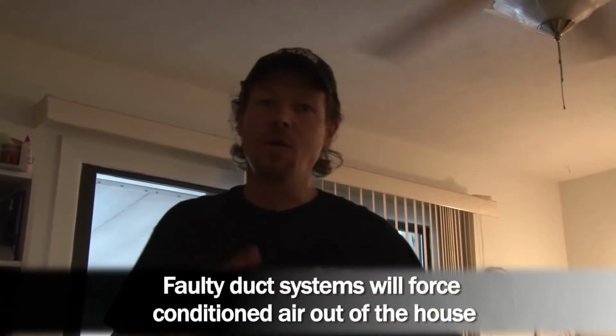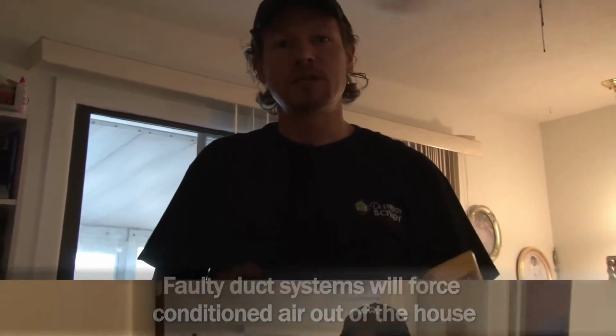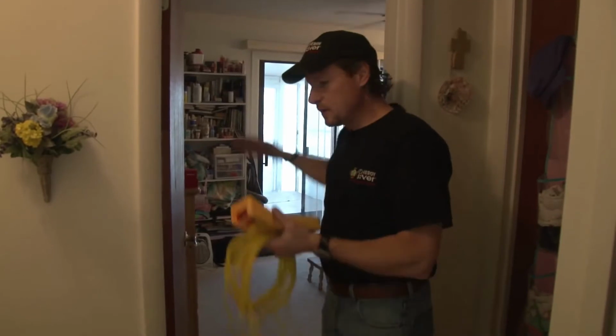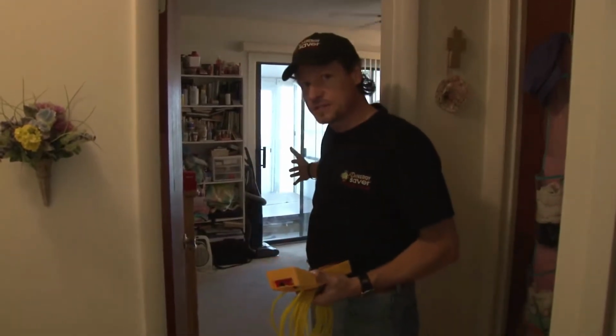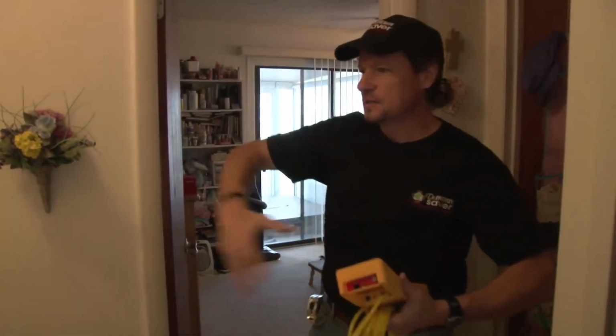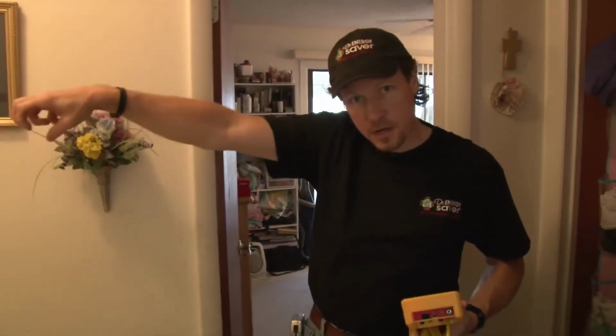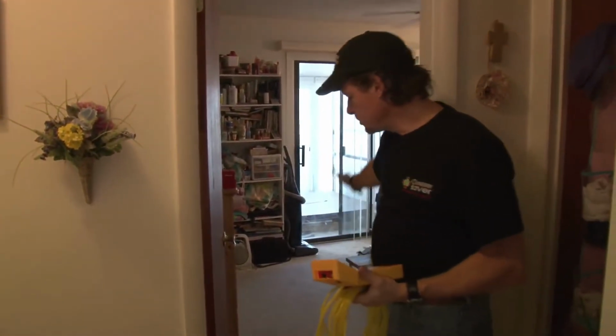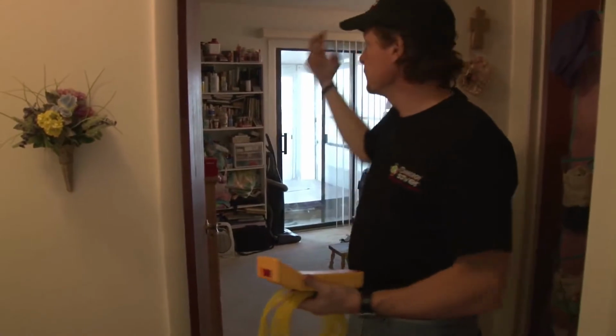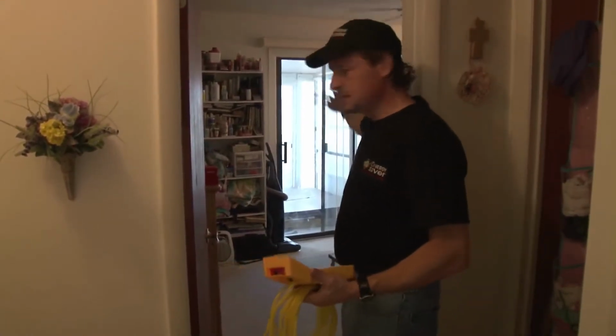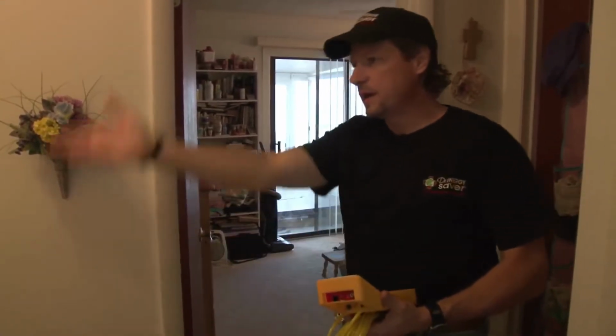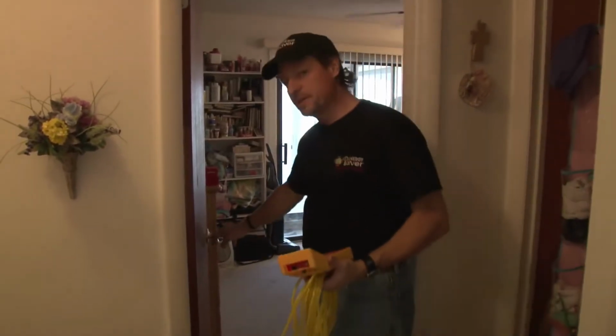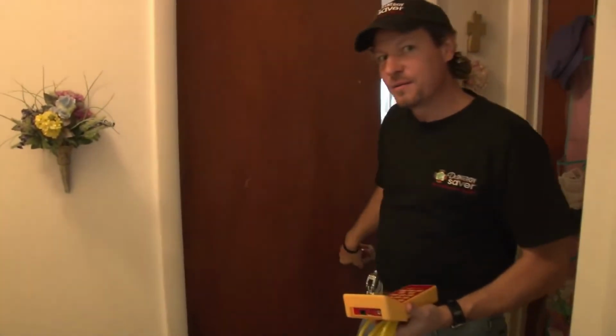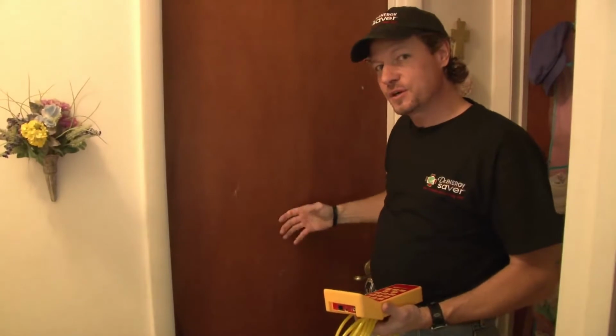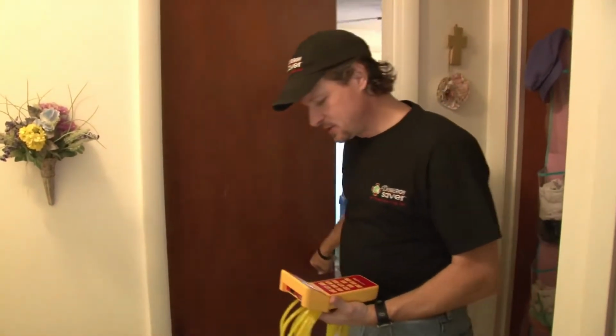Let's measure and quantify this difference in pressure. When this bedroom door is open, the door opening itself serves as the return because the central area is where we're drawing air back to the HVAC system. So this really is our return. The air can come out of the supply duct into the bedroom and run out through the hallway. But the problem is when we close the door. When we close the door, we no longer have a return into that bedroom. And this could be a problem.